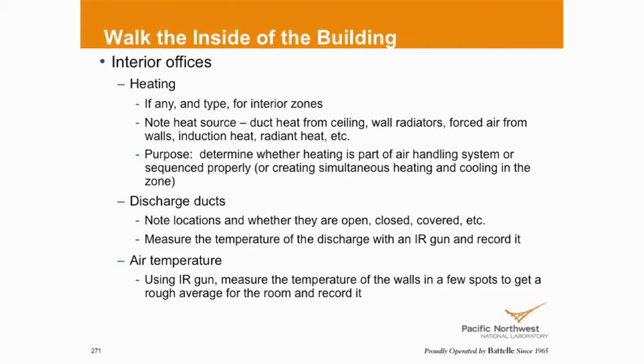Okay, so while we're walking down, we've talked about this already. Do we see wall heaters, ceiling heaters? Are they electrically heated? Are they hot water? Are they interfaced? Are they synchronized with the primary VAV box? We see a lot of buildings that have separate baseboard heating systems. They run on their own. They're not in any way interfaced or integrated with the VAV box controls.